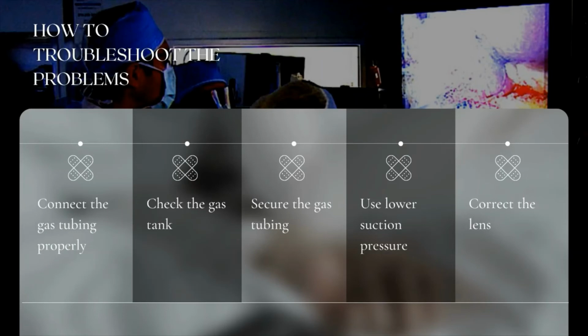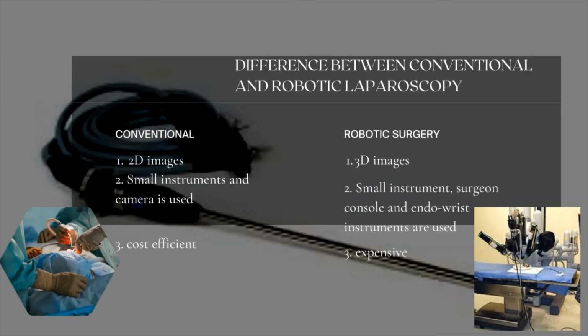If it is empty, change the gas tank. Open the gas valve completely, thereby avoiding issues during surgery, and also secure the gas tubing properly. Use lower suction pressure and allow time to re-inflate. Use high gas insufflation to avoid the problem for an obese patient. Check the connection properly and check the lamp in the light source, as sometimes it may burn out. Clean the connection between the camera and laparoscope and correct the lenses. These are all the troubleshooting steps for the problems.